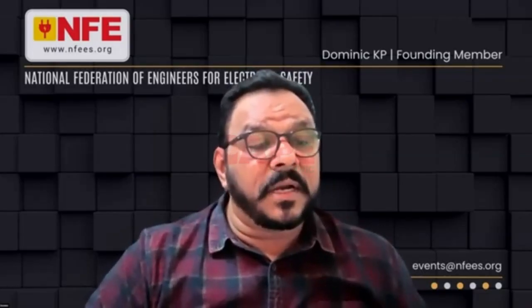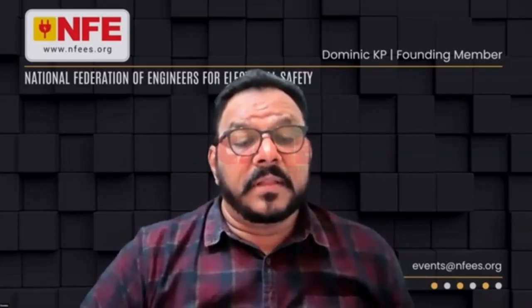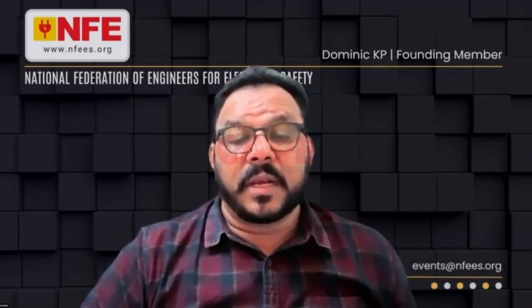Nitin Gorpade asks: against the equipment supplier's demand for copper cable, we lay aluminum cable. That is, against the demand of 10 square mm, we lay 16 square mm aluminum. There can be other reasons why the equipment manufacturer says it. If you're going with a good quality equipment supplier, they will give a ZE value, and you are supposed to achieve that ZE value at the equipment terminal. But sometimes in India, rather than specifying the ZE value, we just say to put aluminum cable or copper cable. I will not be able to comment on this, but going with a higher size, I feel it is okay, but I can't give a specific answer. In terms of safety, it can be higher, or you can ask the supplier to give a rating in aluminum, and you can put the same rating. That's not going to be a difference.